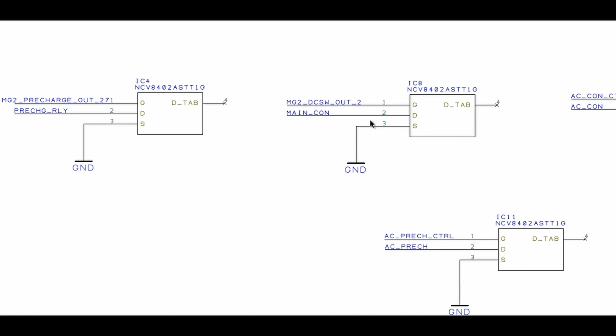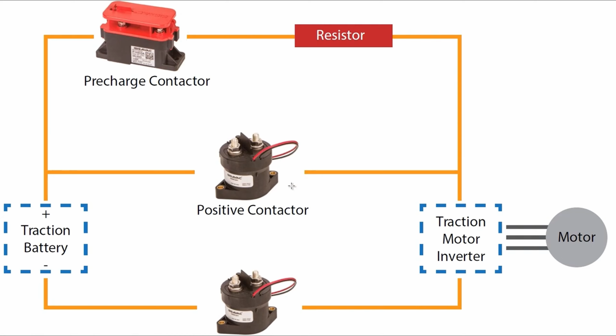We're going to operate a diagram similar to this one, except I will not be using the negative contactor. At the start of the pre-charge cycle, the positive contactor will be open and the pre-charge contactor will be closed. We will then charge the capacitor in the inverter through this pre-charge contactor and resistor. Once we complete the pre-charge cycle, we will open the pre-charge contactor and close the positive contactor. At this stage the current will not be excessive and we do not need a current limiting resistor.